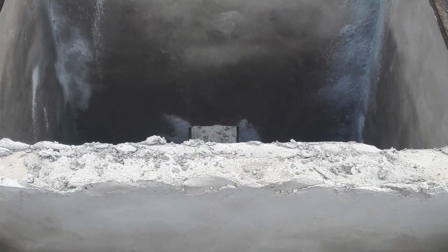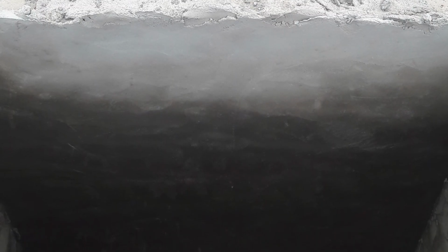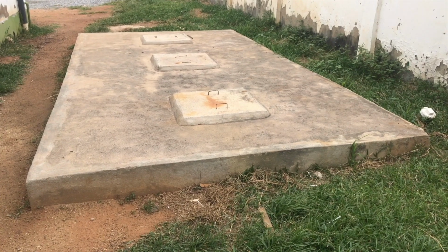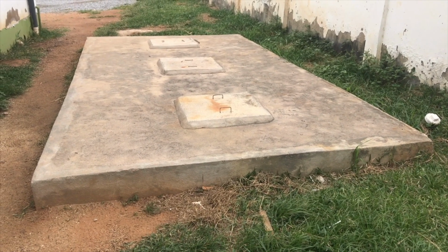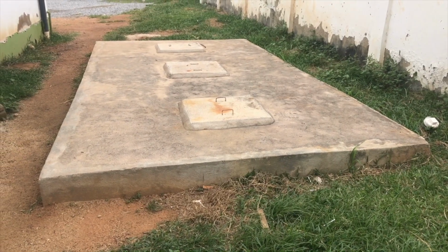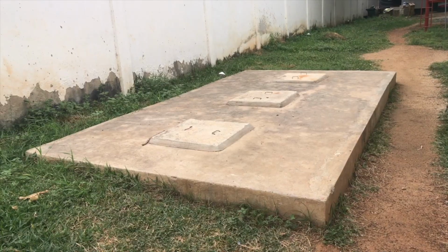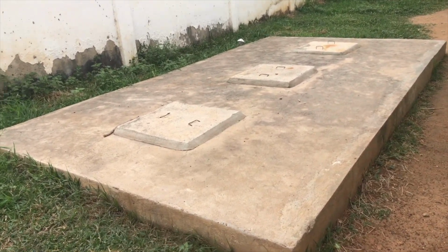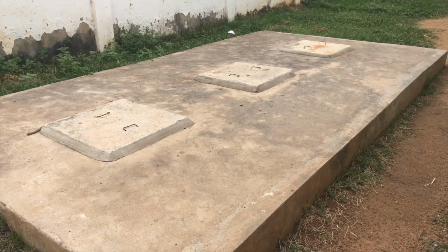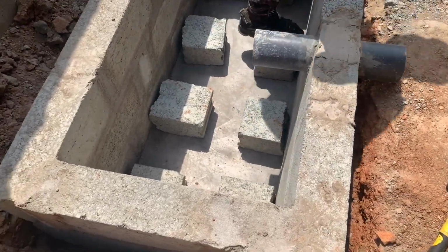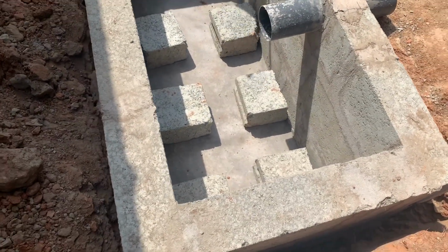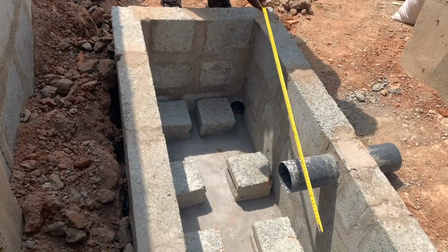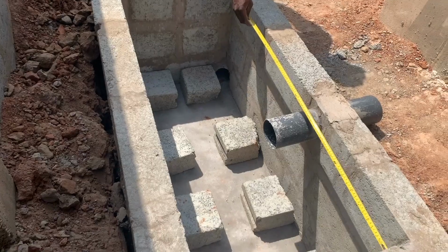So if you, as a Biodigester installer, want to replace that tank with a Biodigester, one of the things you have to look out for is the level of the pipe and how the slope has been designed. If the slope is too steep, then your advice is to ask the homeowner to raise the pipe. And if there is an S-trap seat in the room, you advise them to replace the seat with a P-trap so that the pipe is projected out and you can get a level for the digester. Remember, Biodigesters are not deep. The maximum depth can be about 4 feet. Ideally, it should be 3 feet, and if it's 4 feet, then it's fine.